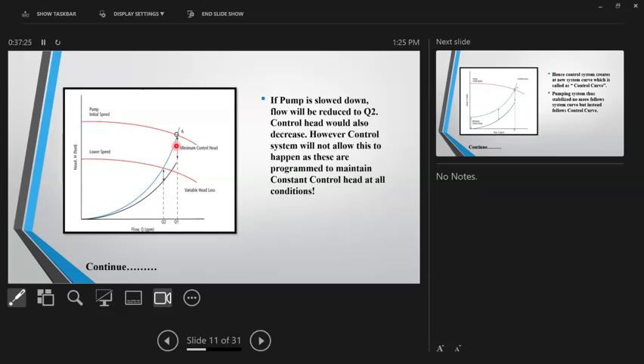Now let's imagine that the AHUs have less load. Yeah. So from this initial condition, let's say it is evening, the office is getting emptied, and the control valves start closing. Now you really don't want Q1, you want Q2, less flow. You would imagine that the pump will straight away come to a speed where it matches Q2, and that's the speed, right? That's our assumption: initially the flow was Q1, the design flow. Now my flow requirement is less, say 70%, 60%. So my speed will come down to where it will intersect this line, and my speed will get settled there.